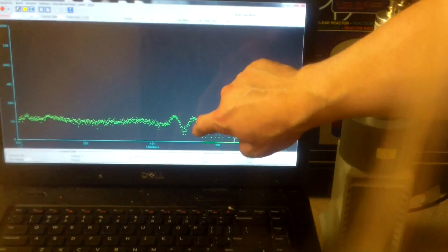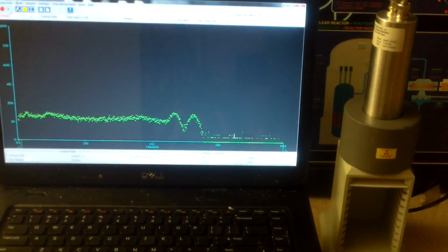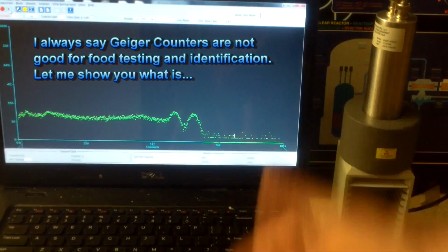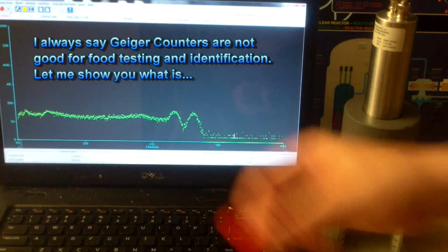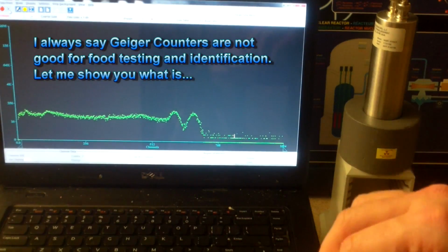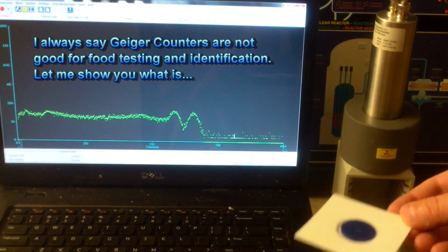And very, very quickly you see these two peaks forming here at 1173 and 1332 keV. These tell you right off the bat that this is cobalt-60. So now we know it's cobalt-60. Alright, so we now know what this is because we can see the energies with this type of detector as opposed to just the specific counts.